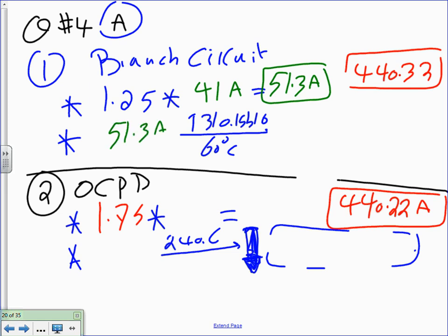Then you're going to take the 51.3 amps. Remember why we go to the 60-degree column? Anybody remember that? Because we're using the NMB cable. That will give me number 6. Number 6? Because 6 was good for 55. So this will be number 6 slash how many? Air conditioning? 2 AWG type NM, NMB cable. That's it.